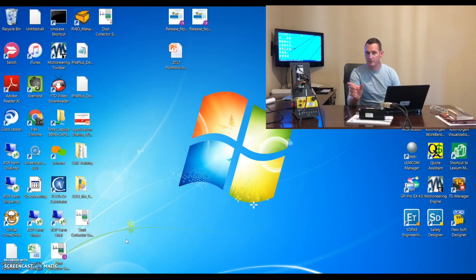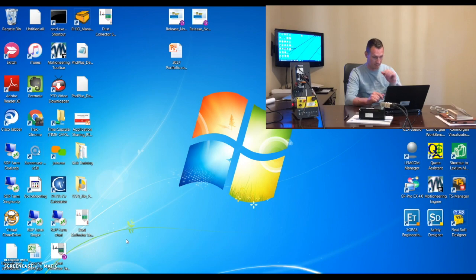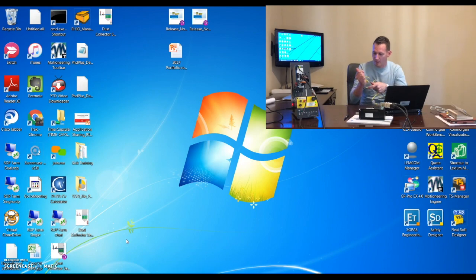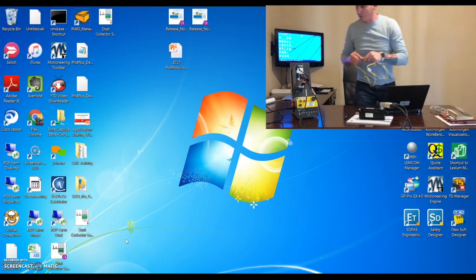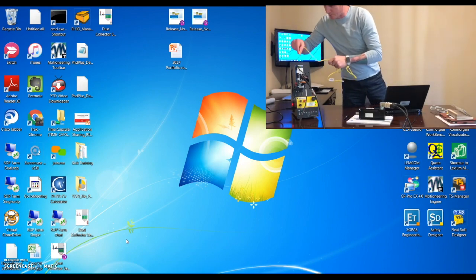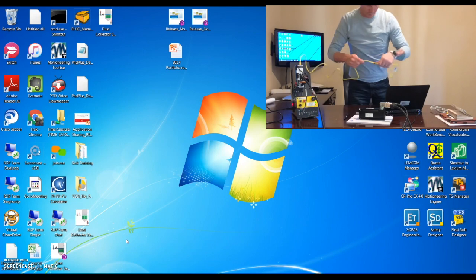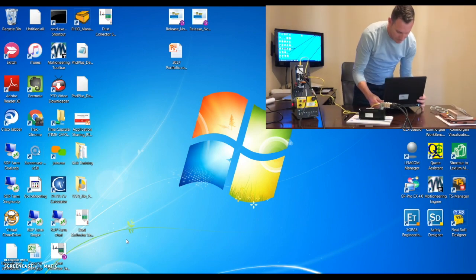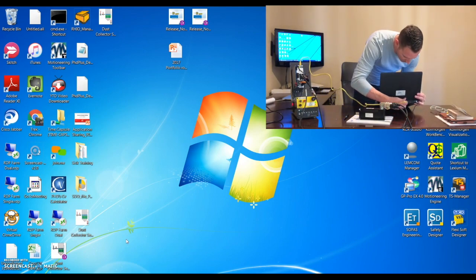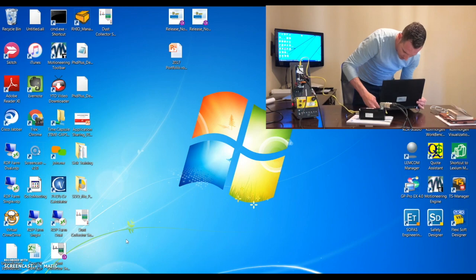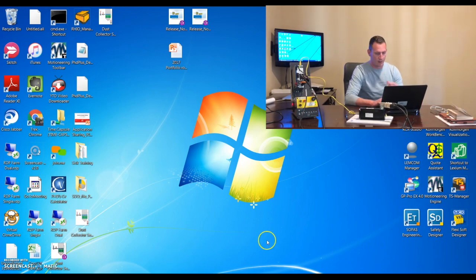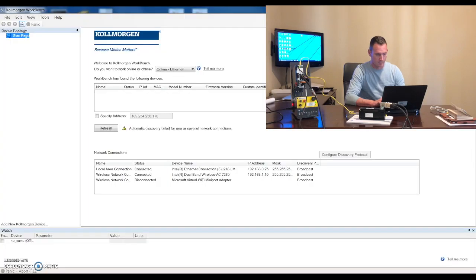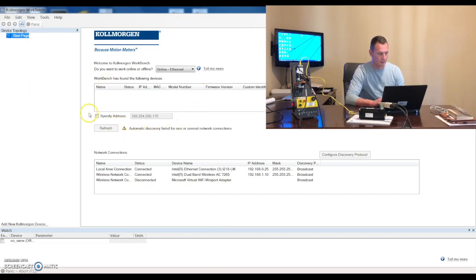So we've got the drive powered on. The next thing we're going to want to do is connect our drive to our computer. So we're going to need to plug in an ethernet cable. Ethernet cable gets plugged in up top at the X11 port. We'll plug that into the back of our computer. From there, we'll open Kollmorgen workbench on the computer. And we'll see if we can find the device. And you can see no device is showing up.